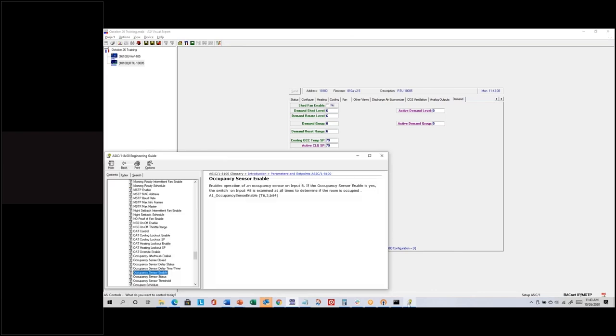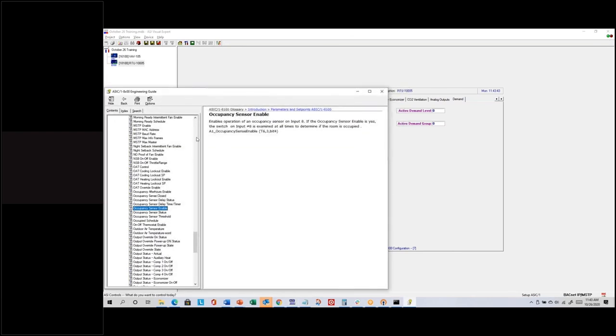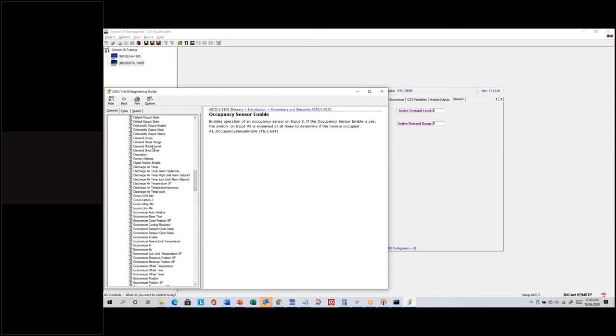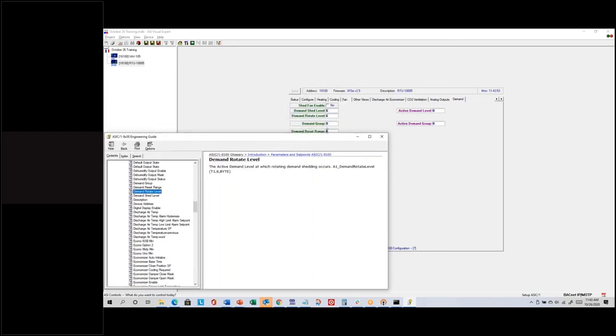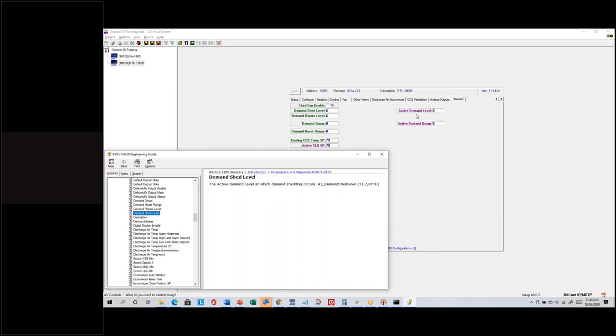That's described in the documentation as well. If you look at demand reset range and demand rotate level: the rotate level is usually lower than the shed level, so when your group is active you shut down first. The demand shed level, regardless of group, sheds fans at that level. These are available in both ASIC ones, but they need to be told the level and group — they won't do their own calculations to determine level and group.